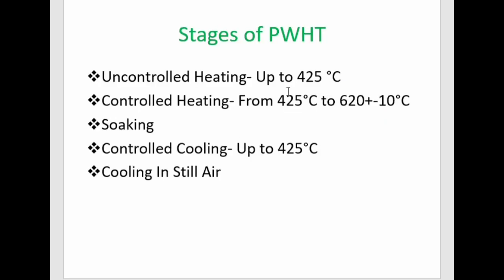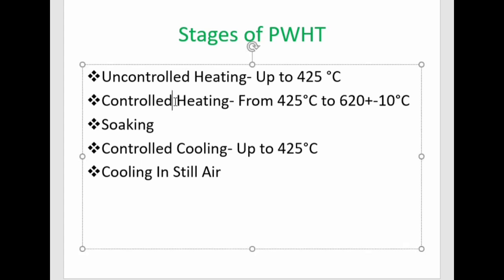Prior to moving into UCS-56, let's look at the stages of PWHT. PWHT is divided into five different steps. The first step is the uncontrolled heating process up to 425 degrees Celsius — that means up to 425°C there is no control on the rate of heating.